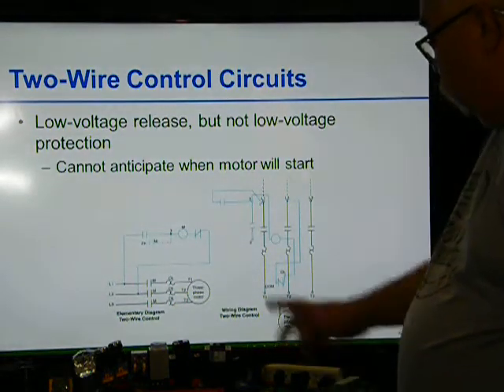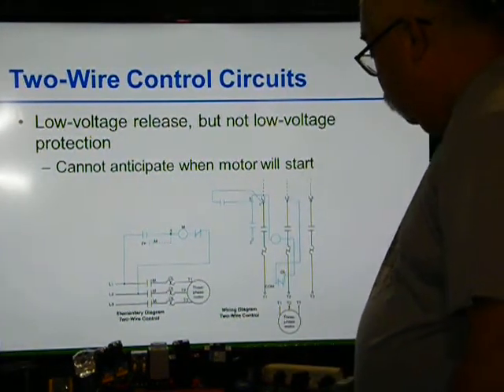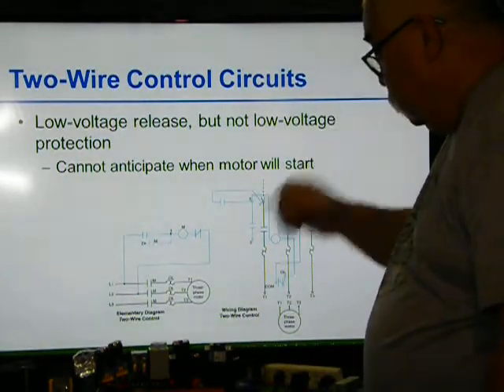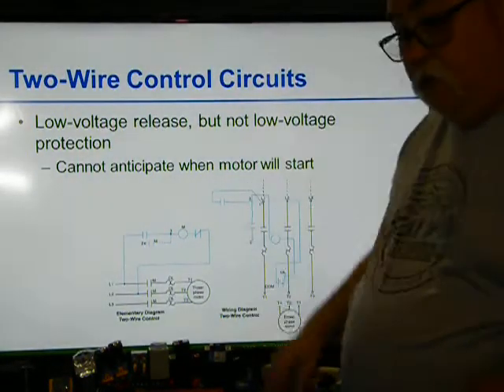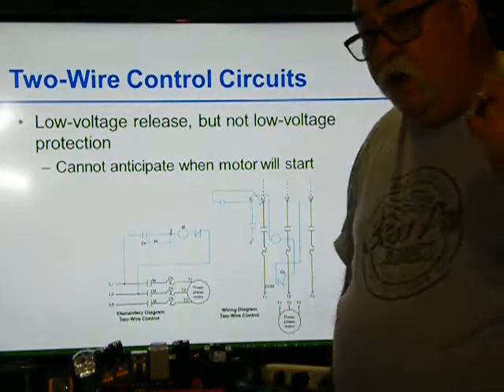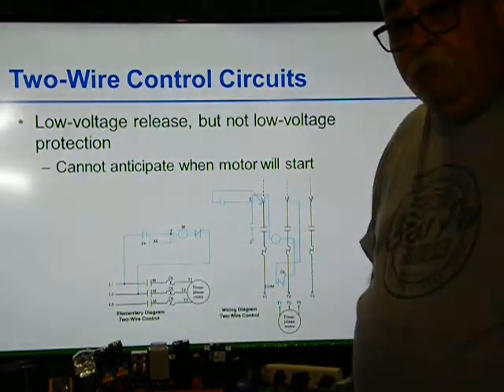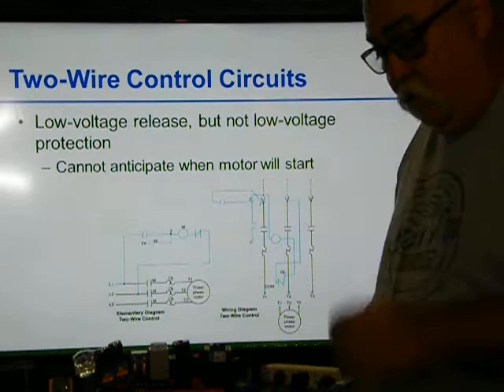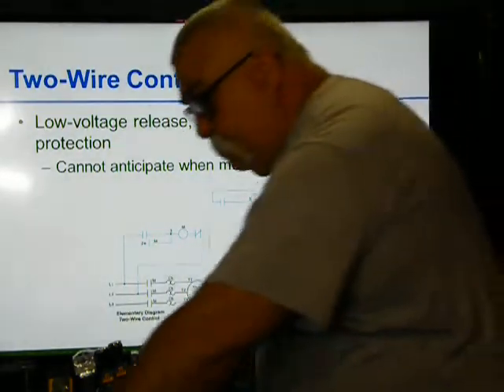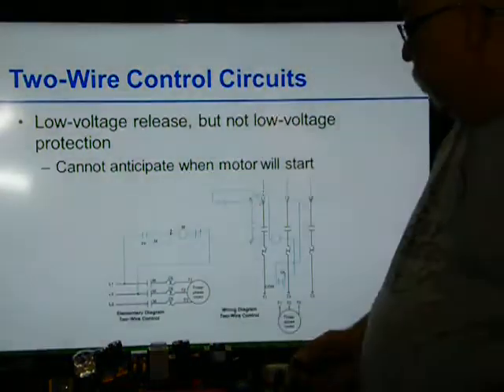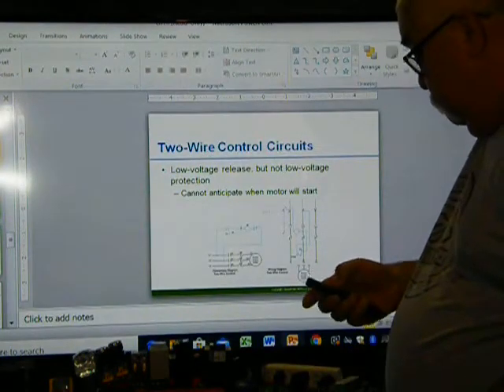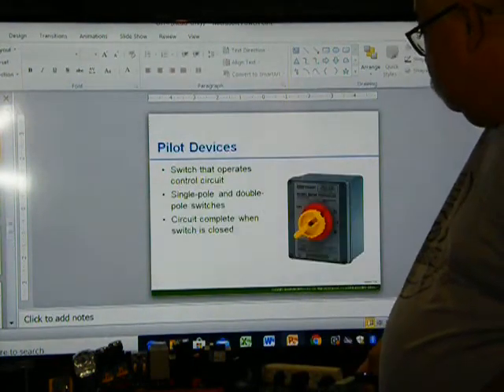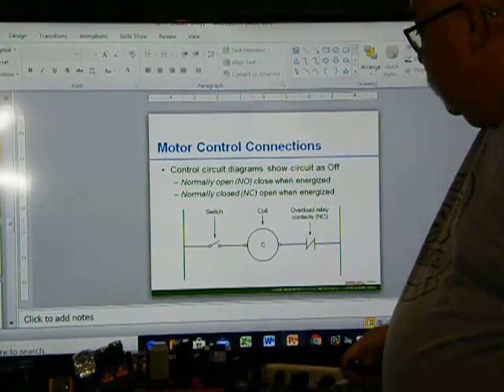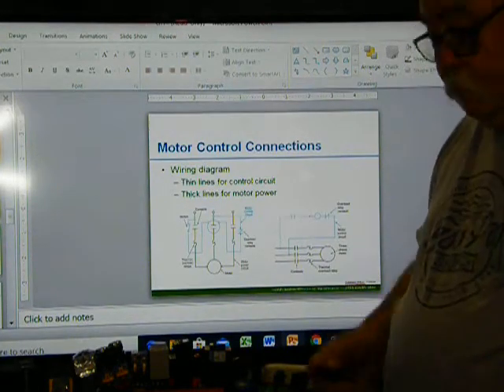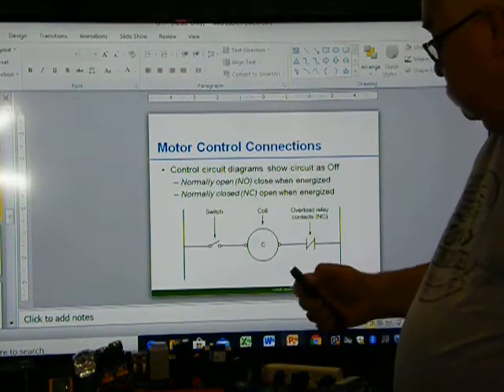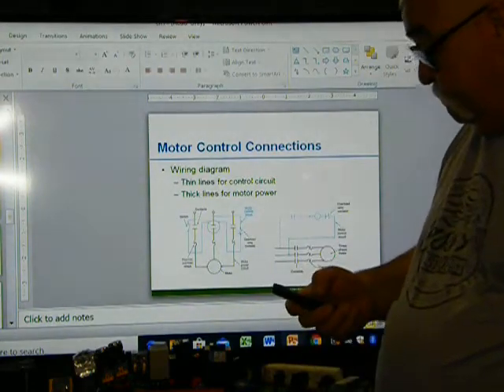Go across. So that's the elementary two-wire control wiring diagram. These are wiring diagrams: one's an elementary, one's a two-wire, but for the most part this is still a wiring diagram. So you have a wiring diagram, and you have a ladder, which is the schematic. This is a wiring diagram. There's your ladder, and that's a wiring diagram. Your ladder and your wiring diagram.